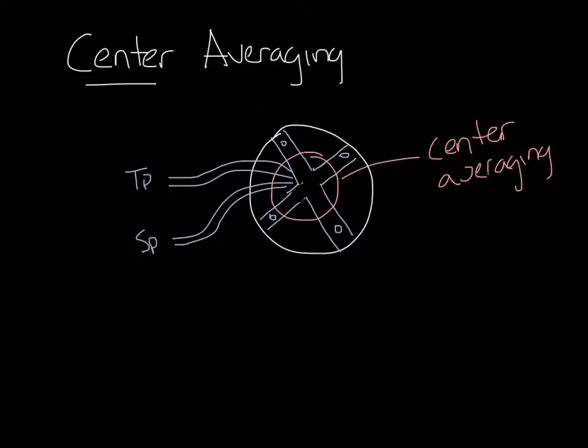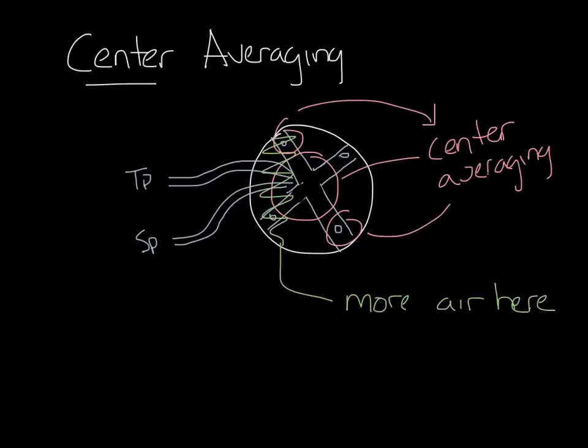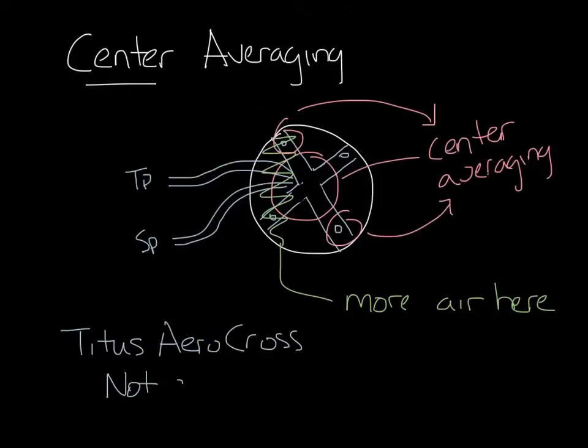Now if there are poor inlet conditions and the air piles up on the left side of the inlet like it did in the last one in this green area, the readings from the hole on the left, which is reading high, and the hole on the right, which is reading low, are going to be averaged in the center of the flow sensor and give a more accurate signal to the controller. This means that VAV boxes with center averaging flow sensors, like the Titus Aerocross, are not affected by poor inlet conditions as much as linear averaging sensors are.